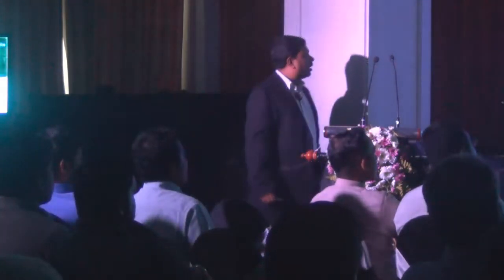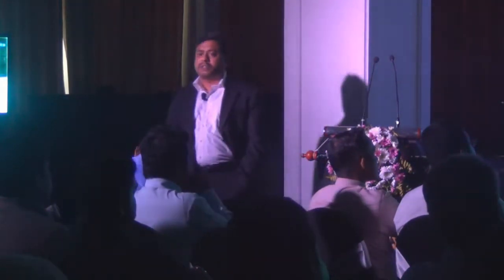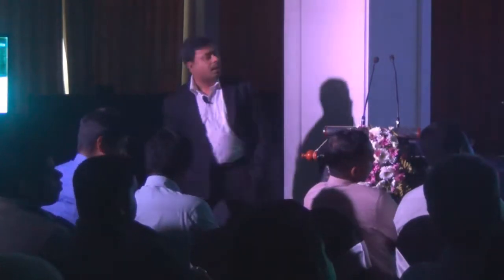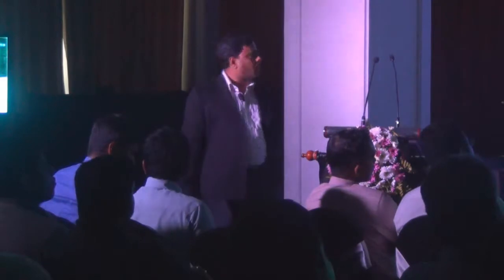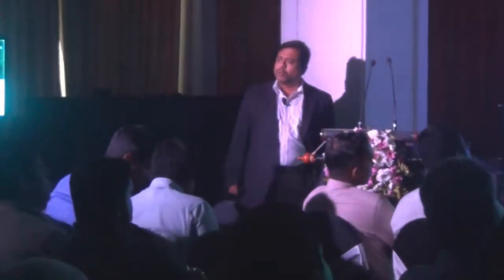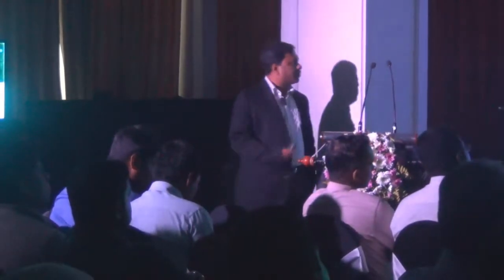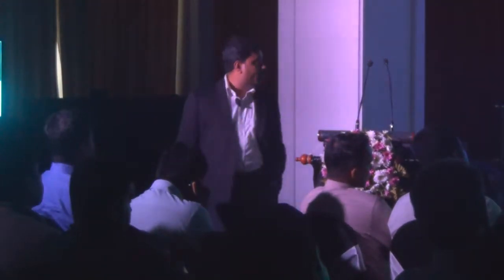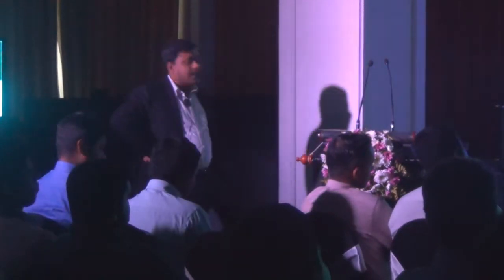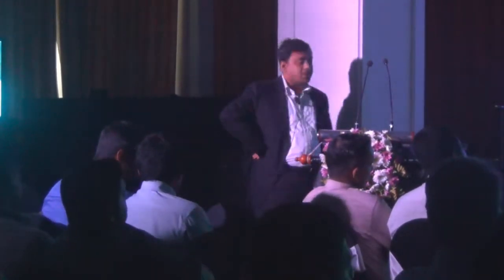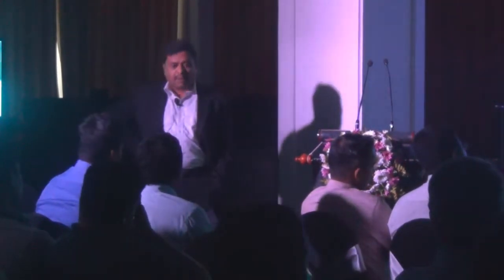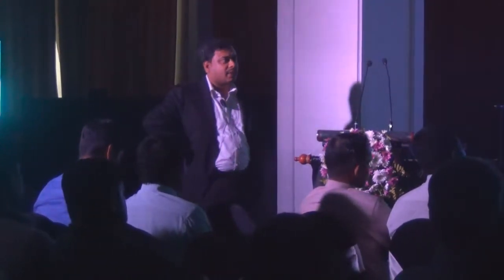Then comes Liebert NX. This is completely one more level of UPS systems, which has an IGBT rectifier and IGBT inverter on both sides, and it has a very high efficiency, again 95.3%. It has dynamic flexibility, with very high input voltage and frequency tolerance that it is able to withstand. And it is very compact in size; if you see the size of the 250 kVA, it is very compact. Up to 800 kVA, the size is a very small footprint. High power density: it is capable of delivering an output power factor of 0.9, so even an 800 kVA can deliver 720 kilowatt. And for infrastructure management, advanced communication options are available. You can monitor sitting anywhere, and you can access the complete UPS system.